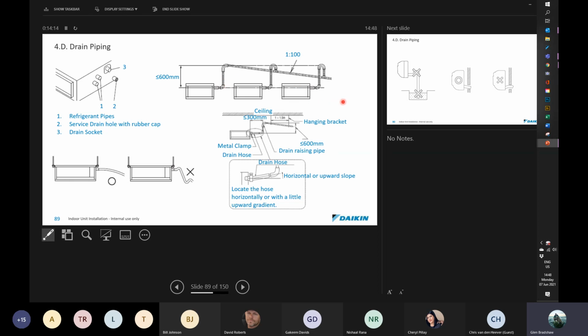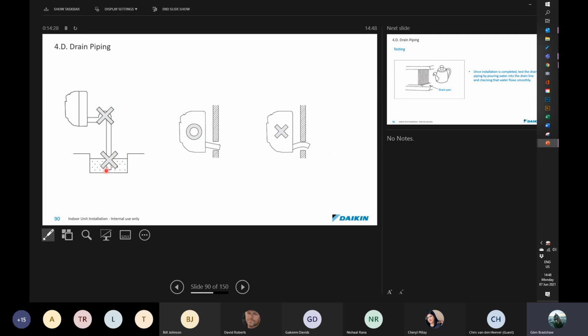common drains. Remember, if you are going to come out of the unit, come out smoothly. If there's no drain, you're going down. Don't allow for zigzagging in your pipework. It's only going to cause more problems for you. Ensure that the end of the drain is able to release the water. Don't place it into sand or something where it's just going to back up and eventually cause a leak inside.